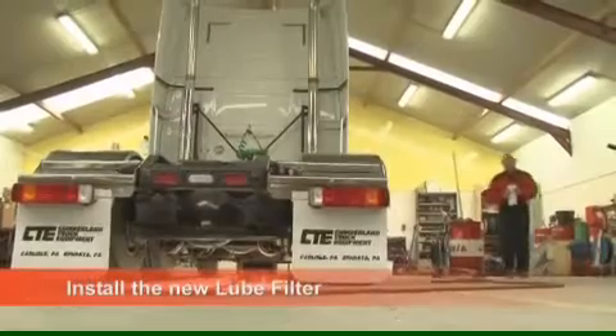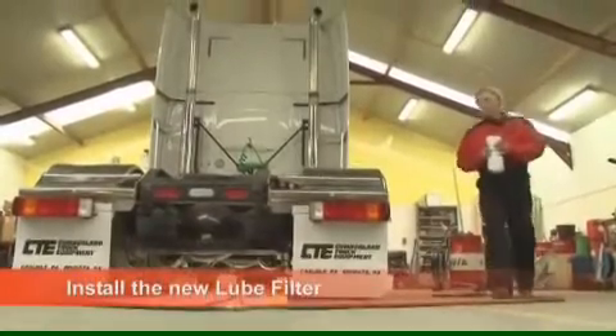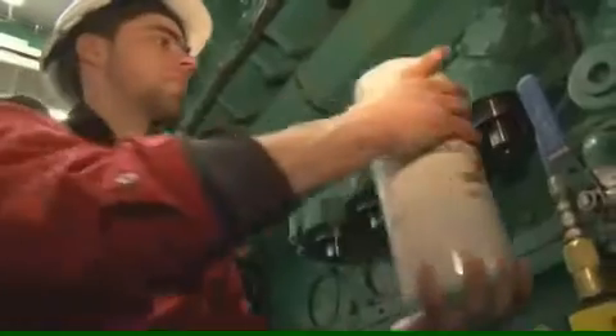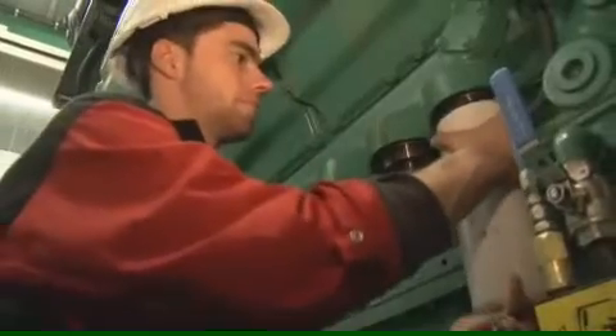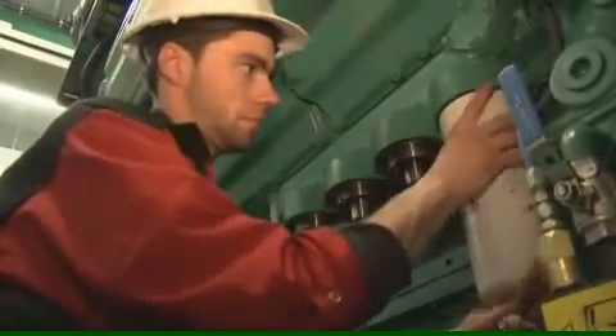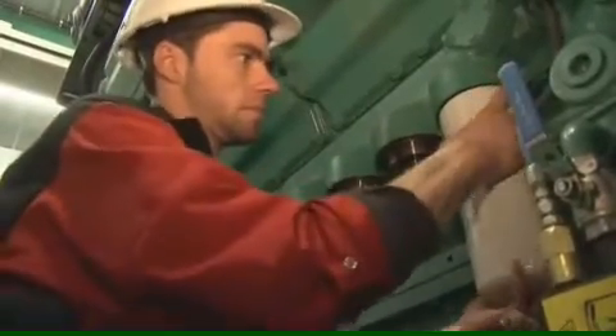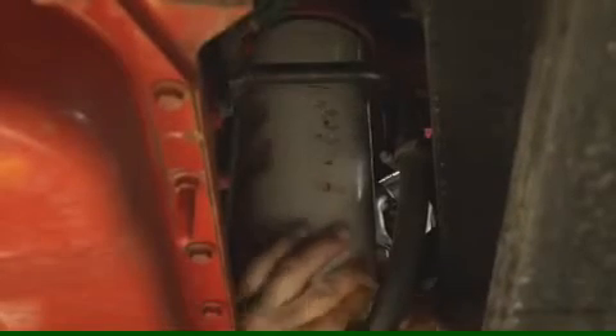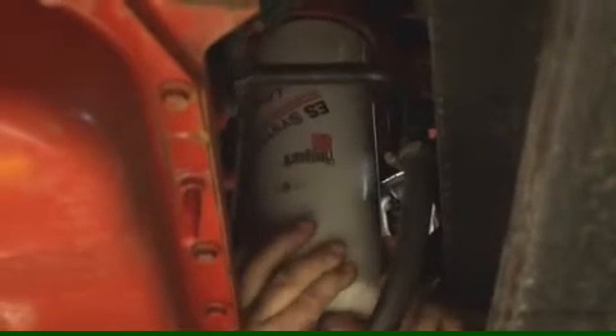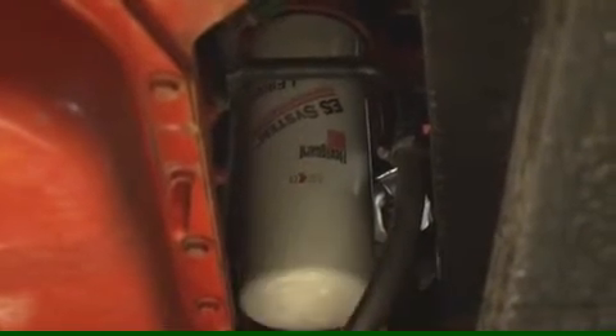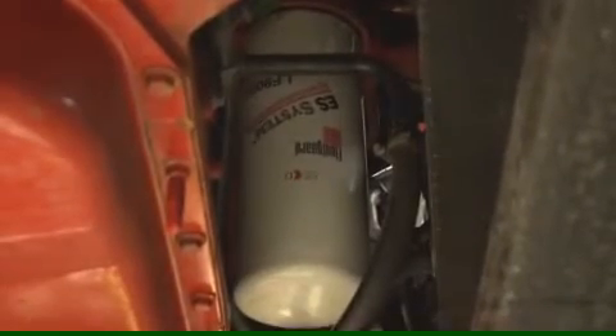Take the pre-filled lube filter, including all the necessary gaskets and seals, and screw the filter onto the filter head. Prior to that, always check the installation pictograms again to see how much tightening the filter requires. Most filters require 3/4 or 1, which means 3/4 of a turn after first gasket or seal contact with the head, or, in case a 1 is indicated on the pictogram, a full 360 degrees of rotation after the point of first gasket or seal contact with the sealing surface of the filter head.